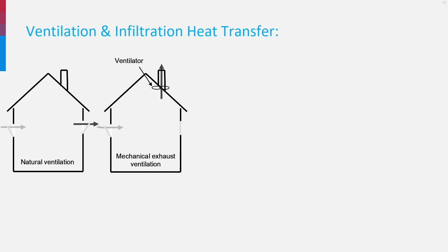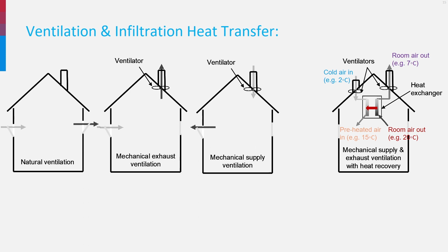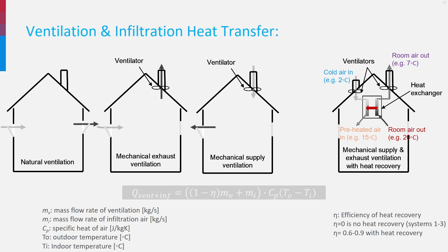You can place a ventilator, a fan, to push the air out of the building. You can also use a ventilator to push the air in the building. It then creates an overpressure by which the air automatically goes out through the chimney or the window. And finally, we have the balance system, in which there are 2 ventilators, one for supply, one for exhaust. The main advantage is that heat recovery is possible, as indicated by this arrow. It saves lots of energy. To calculate the heat transfer due to ventilation and infiltration, you can use this equation.